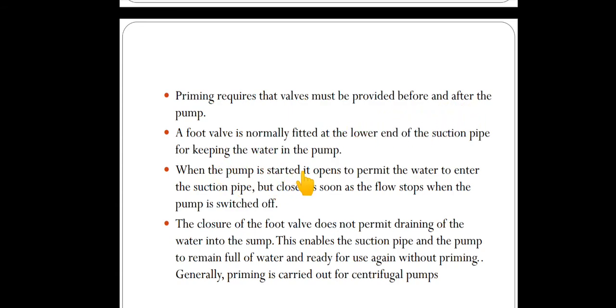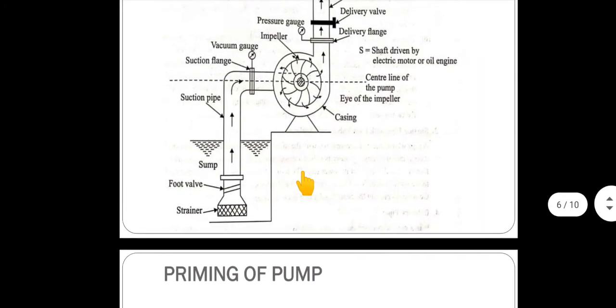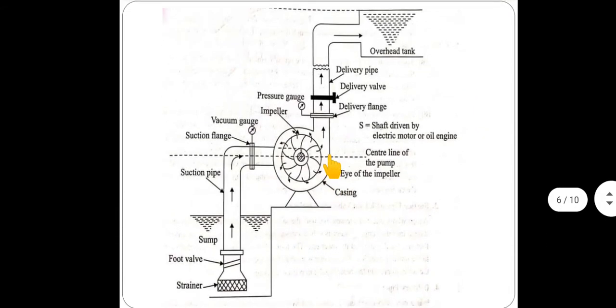So the foot valve. Coming to this diagram, what is the function of this foot valve? See, when we start this pump initially, when we first install it new, what do we have to do? We should fill this up with water. We should pour the water and fill this up. And we cannot do this daily. So what we can do is place this foot valve.